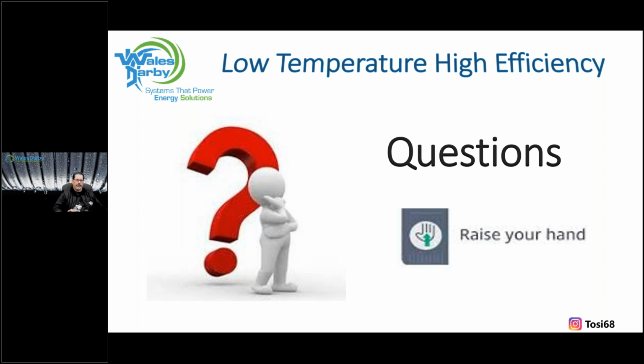Going back to fossil fuel, like, how do we do this again? I'm just doing boilers, how do I make it better? Yeah, I do the closely spaced tees, I'm doing the better venting, I got the magnet, I'm tapping into something, talking about lowering water temperatures. Because if you do it currently with what you're already established with, going forward you might be a non-believer before you become a believer, simply because I'm telling you, you need to be in that 120 to 130 degree system design temperature for water. And you're gonna go, no way, never gonna happen.